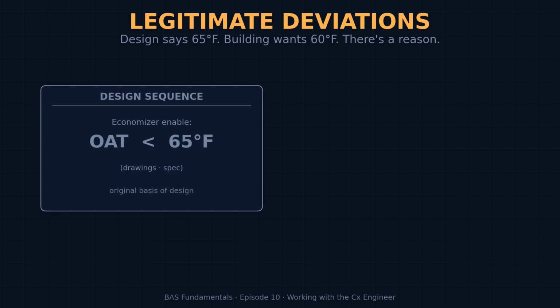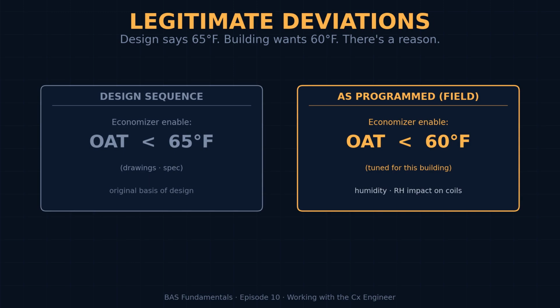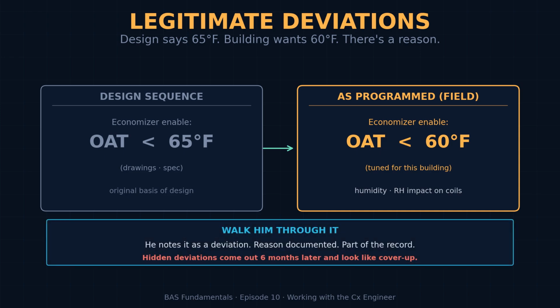Another one. Sequences of operation are rarely programmed exactly as written. They're interpreted, and some of that interpretation is legitimate field adjustment. If the design sequence says the economizer enables below 65 degrees, but the building actually needs it to enable at 60, there may be a real reason. Walk him through it. Don't hide it. He will note it as a deviation, document the reason, and it becomes part of the record. Hidden deviations come out 6 months later and look like cover-up.